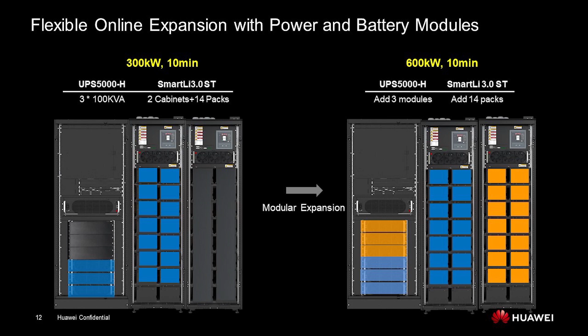separately and intelligently. For example, we have the left photo here. It's 300 kilowatts, 10 minutes for the first phase. And we use UPS 5000 with 3 100 kVA power modules and 2 cabinets of SmartLi 3.0, but only 1 cabinet is configured with the battery modules. After the load goes higher, we can expand online. 3 more UPS power modules are added, and 14 more battery packs are added too. So in the right photo, the blue modules and the orange modules can operate together, especially the battery packs. The system can control the charge and discharge current based on the state of health.